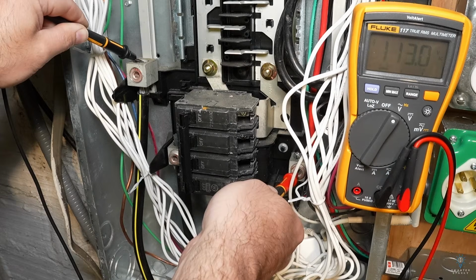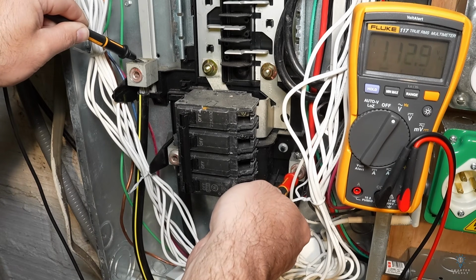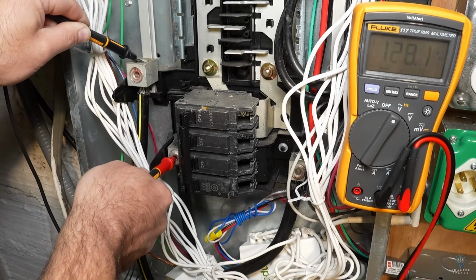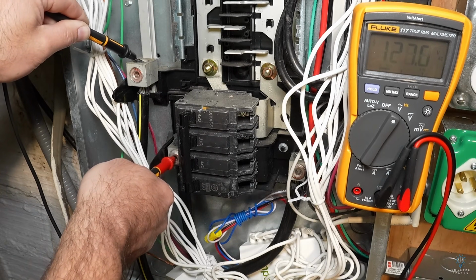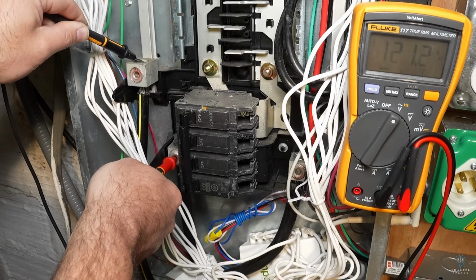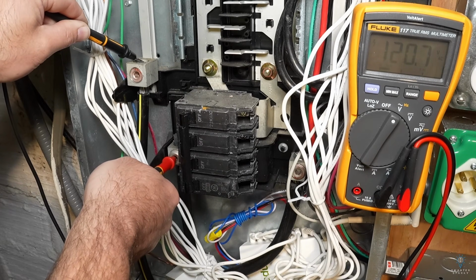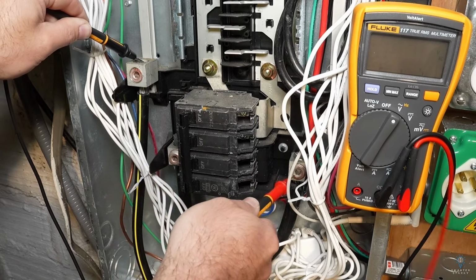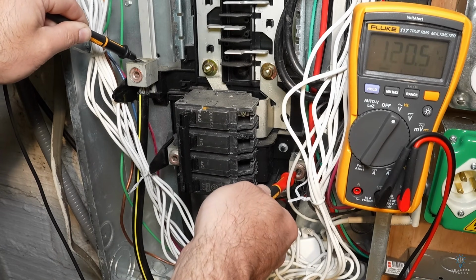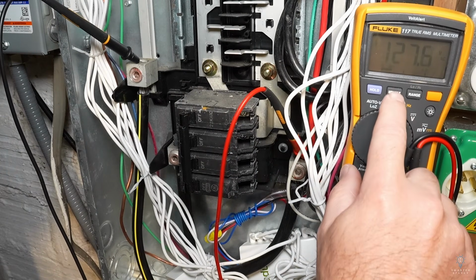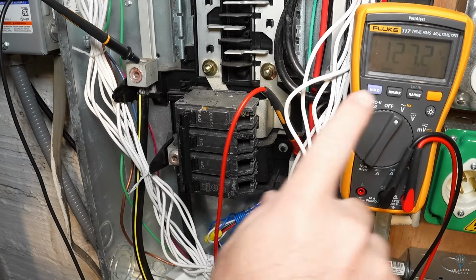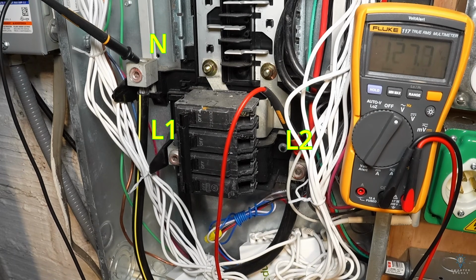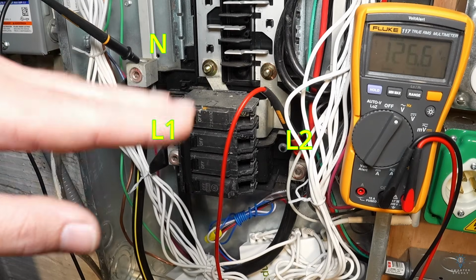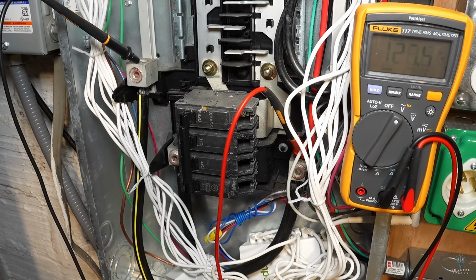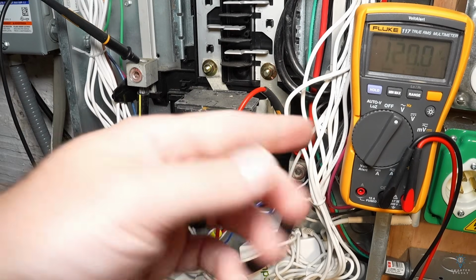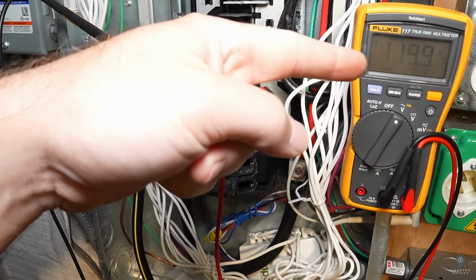Oh, there it just dropped. 113. So this must be higher now. It is. Now we're up to 127 over here. That is very indicative of a loose neutral. Now we're back down to 120, so this is also probably 120. It is. And we're going to monitor this voltage, and I'm going to set the meter to read min-max. So what this is going to do is start logging data and figure out what the minimum voltage is and the maximum voltage is over a period of time. I'm just going to let that run for a couple minutes here. If you did not have a multimeter that has min and max on it, you're able to just watch the voltages fluctuate.